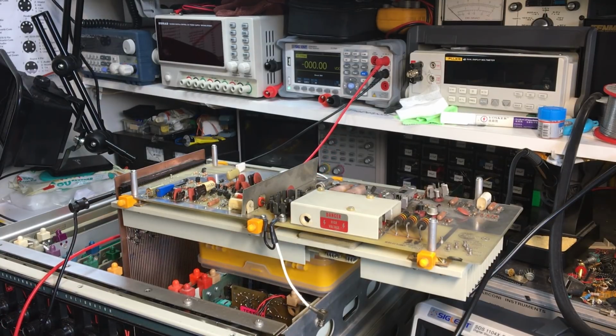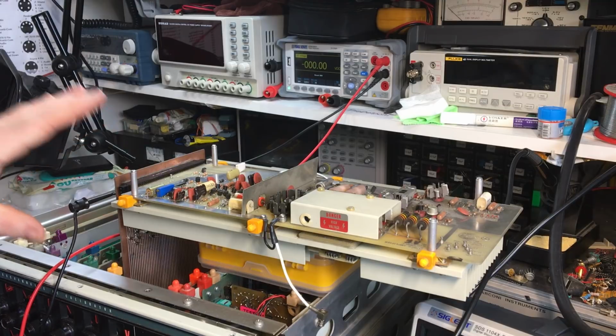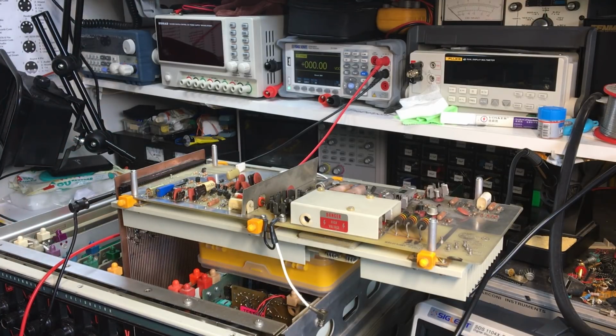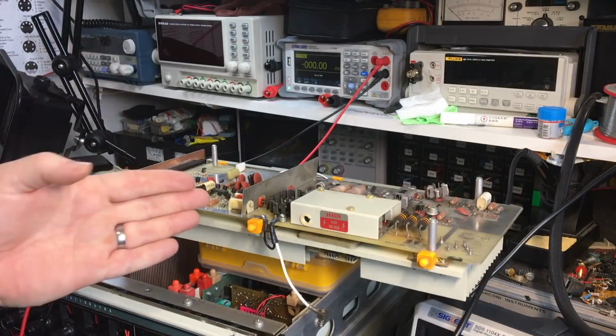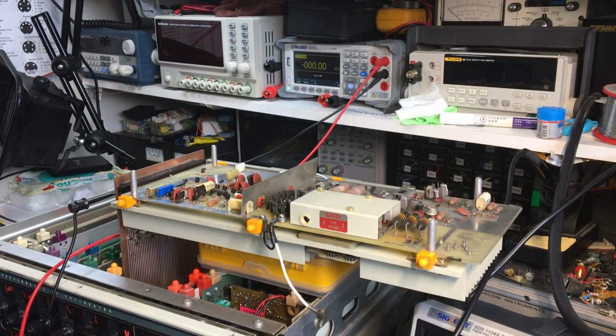Also check out okay. Now there's a note here about pin 79 voltage at plus 15 volt being adjusted to suit the 185 volt supply. If that supply is a bit low, that 15 volt gets adjusted in order to bring that 185 volt supply up a little bit, if necessary. That's later on in the procedure for 185 volts, so I won't know until I get that far. So at least at this point all the voltages check out okay, so at least I know the supplies going to this card are all good. Although I already believed they were anyway.